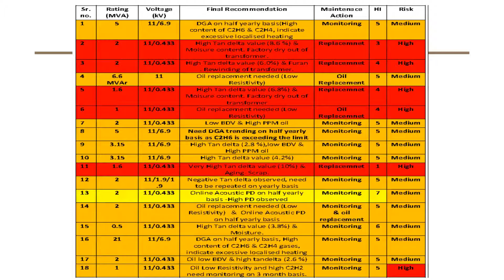So for the same 100 transformers, now in terms of health index, green is not shown here. What you're seeing is all red and yellow indications, along with the health index number and the risk. Risk is high, medium, or low depending on where it is and its impact on the system. So everything is calculated for the fleet assessment.